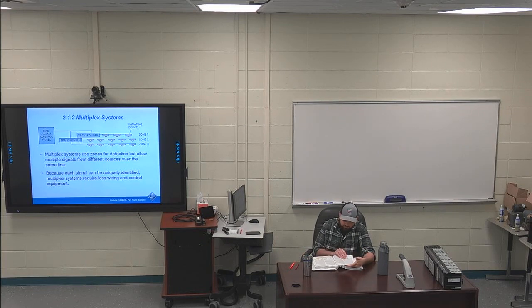Go into 213, addressable intelligent systems. There's going to be a regular addressable system that just has addressable smoke alarms and fire detection, and then you can have analog addressable systems. So two different ones in one section. My next highlight's on page 8. I don't have anything about just the addressable systems, but the step up from that is the analog addressable systems. If you look at page 8, right hand side of the page, the second full paragraph, first sentence is highlighted: most analog addressable systems operate on a 2-conductor circuit.